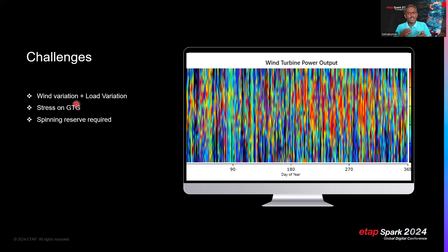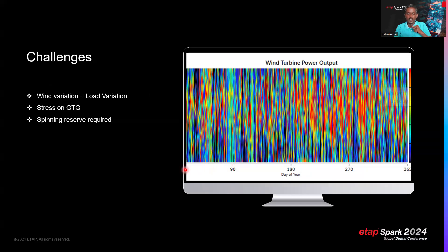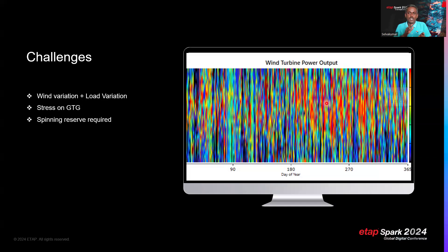Originally, an FPSO has an almost constant power load, with the governor managing frequency by adjusting fuel input. Now there is wind variation on top of load variation. A Homer Pro simulation plots 365 days on the x-axis and 24 hours on the y-axis, with color indicating wind turbine power output — red being highest, black being zero — clearly showing the highly intermittent and variable nature of wind power.